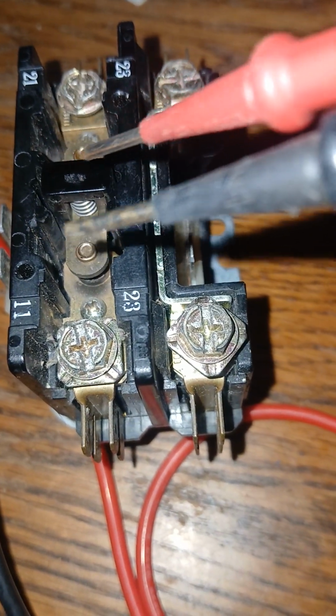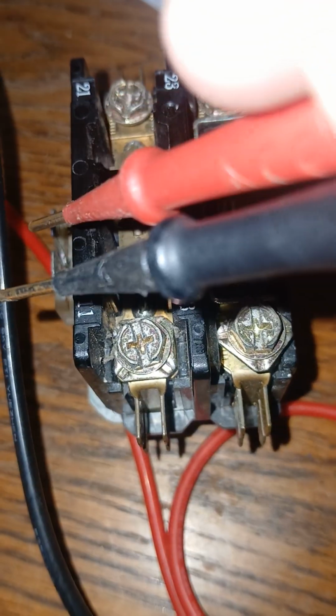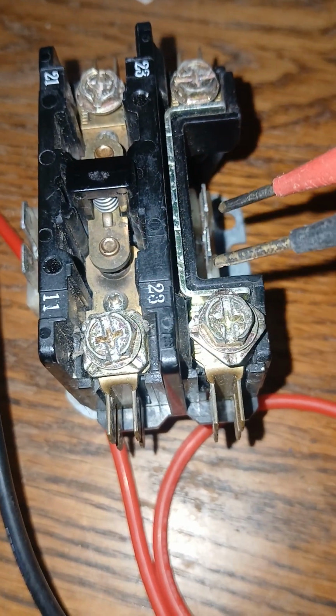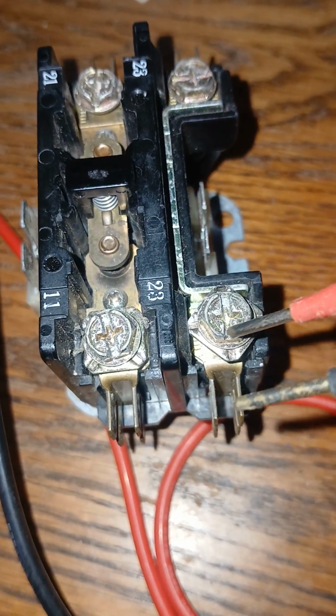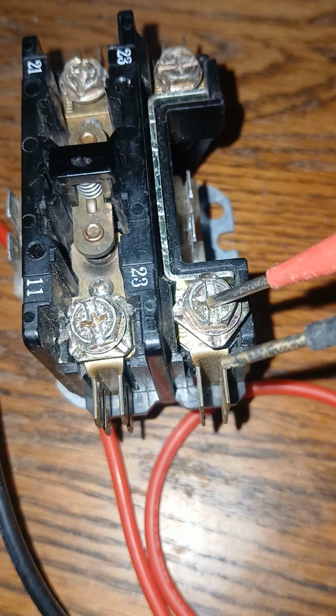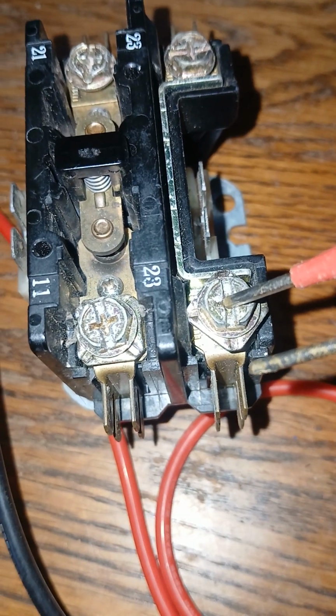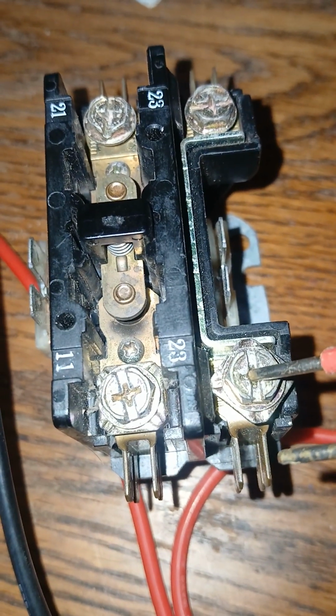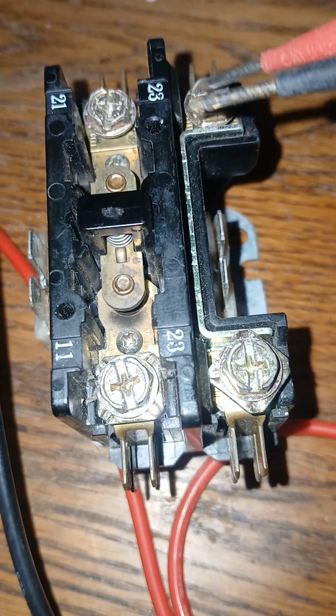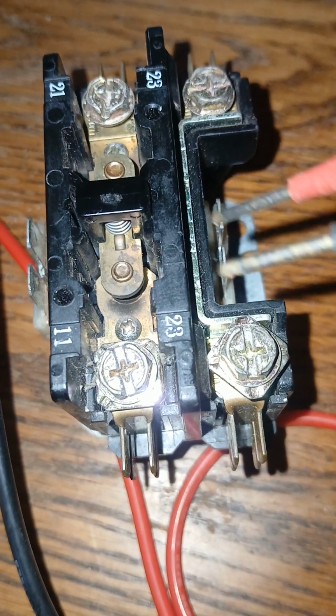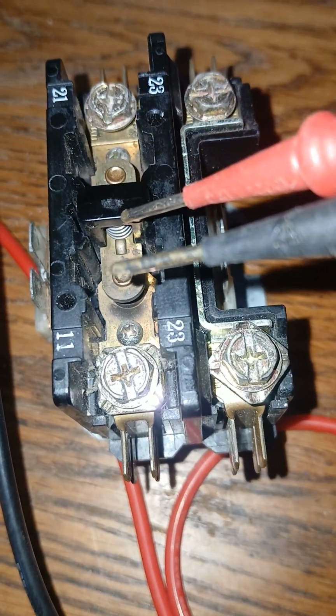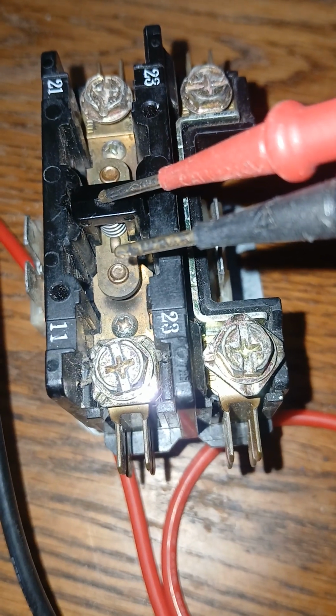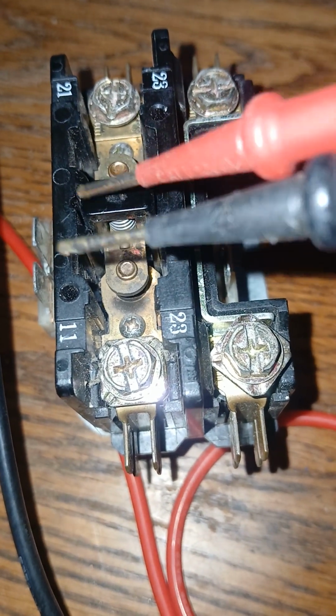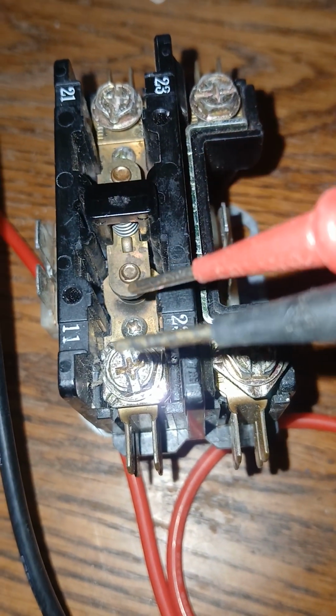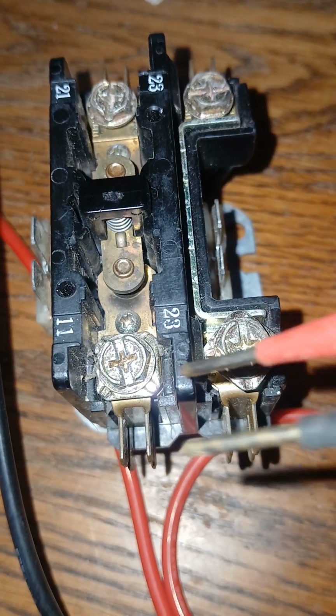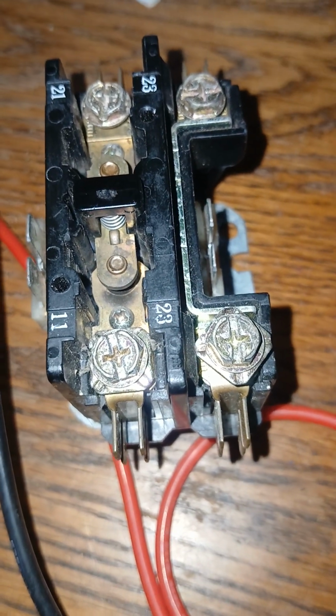If the low voltage, which is on each side of the contactor, is not energized, then the voltage may be here. You may read 240 here, providing that the breaker and the electricity is fine getting to the system, but you may read nothing over here. But once this is energized, then say hypothetically this pulls down, it energizes the coil and pulls this down. Once it pulls down, this metal touches this, so this electricity here goes to here.